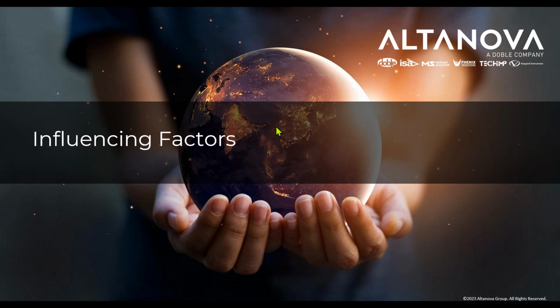Okay, so I would like to now talk about influencing factors. Influencing factors are factors which will make changes to your traces if these factors are present. So you need to be careful how you test the transformer, and you need to be aware of these factors so that when you test the transformer, you know exactly in what condition it was tested. Especially if you compare with previous results or reference results, you have to know how the reference transformer was tested in order to reproduce the same test conditions.